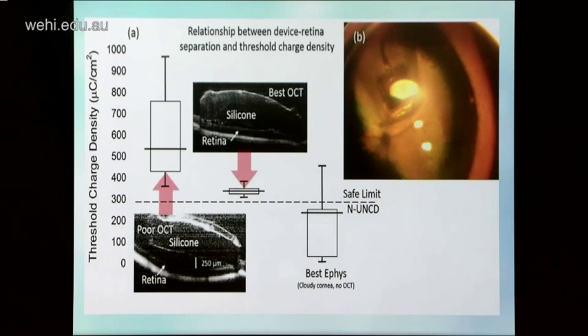These are the three results that we did get trying this experiment. This is essentially what we got. Experiment 1, Experiment 2, Experiment 3. So these are the threshold charge. This is where we got 50% up that curve, so halfway through the maximum saturation. This is the spread of results for all of the electrodes that we tried on that array. So this is our safe limit here. Our first set of data showed that all of the thresholds were above our self-imposed safety limit. The second experiment that was successful, we were getting closer, and then our best experiment, we had all bar 2 electrodes down in the safe zone.